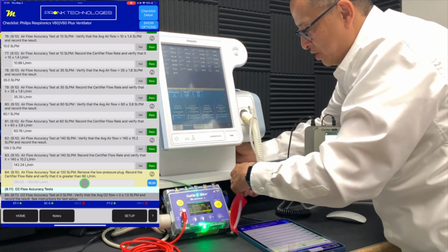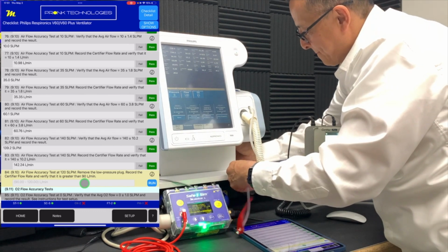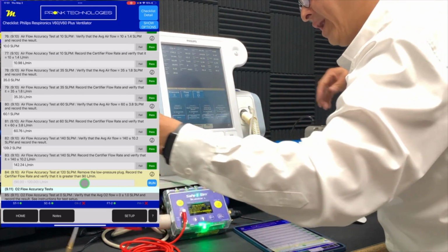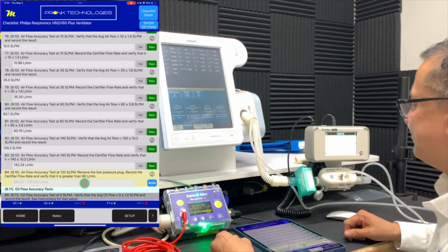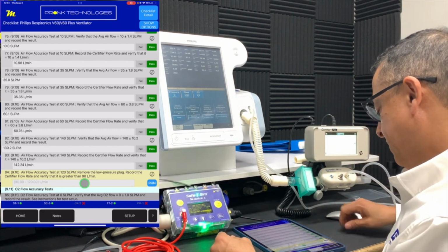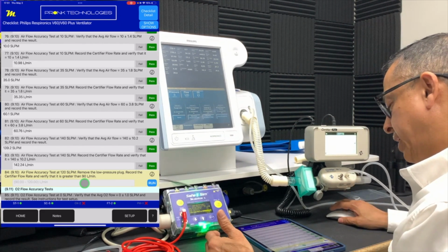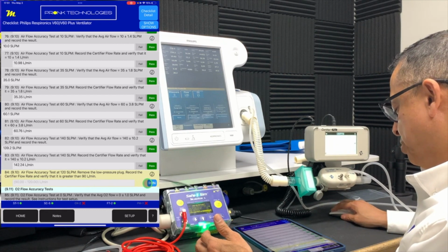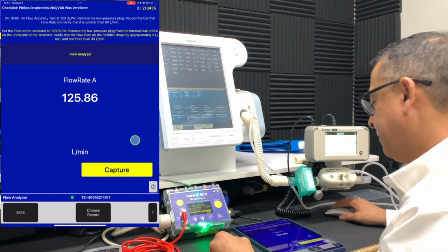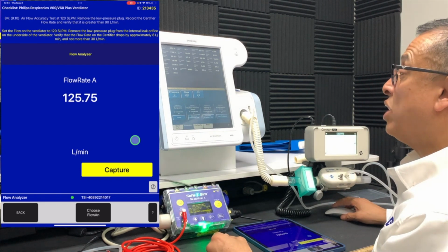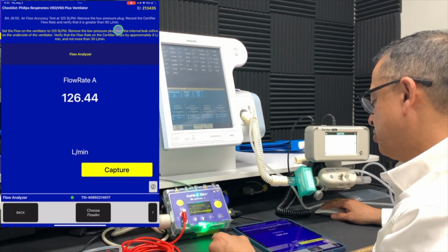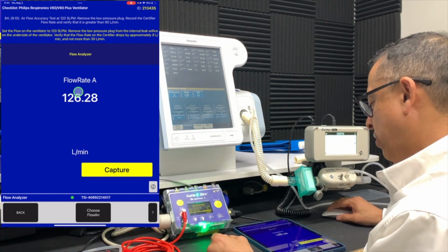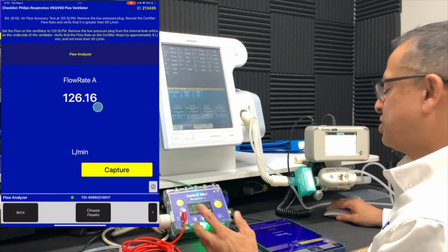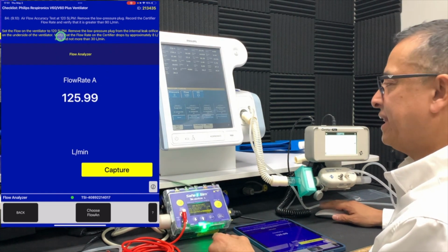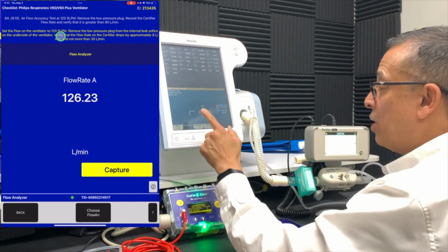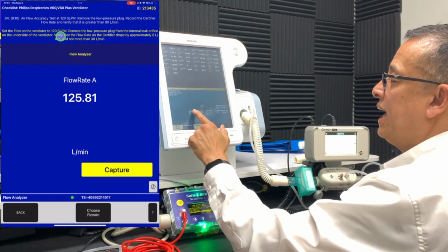A little tricky to do this with the ventilator horizontal. Okay, you can hear that the flow changed slightly. So now I want to capture and see what the certifier measures with that plug removed. And we should be over 90 liters per minute, and we're at 126. So that's good, but I needed to make sure I set the vent to 120, which I still have it set to 140, so I'm going to go ahead and do that.